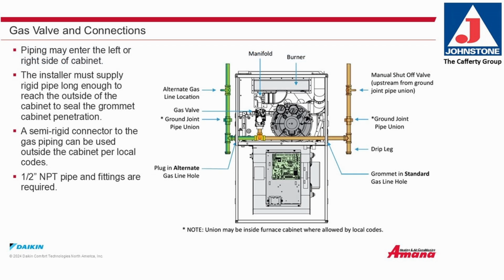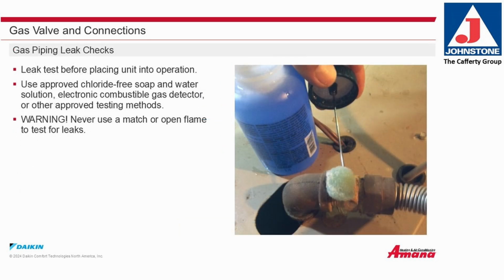Gas valve and connections. Gas piping may enter the cabinet from the right or left side. The installer must supply rigid pipe long enough to reach the outside of the cabinet to seal the grommet in the cabinet penetration. A semi-rigid connector to the gas pipe can be used outside the cabinet if allowed by local code. Half-inch NPT pipe and fittings are required. A union may be inside the furnace cabinet if allowed by local codes. Gas piping leak checks. Leak test before placing the unit into operation.